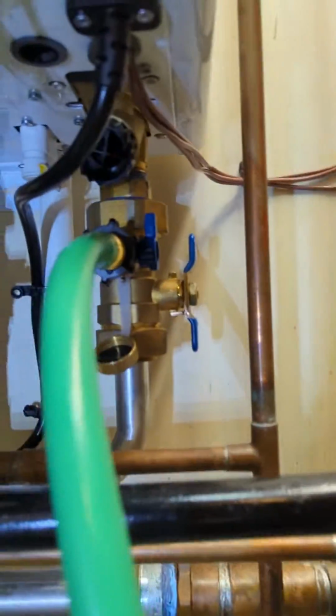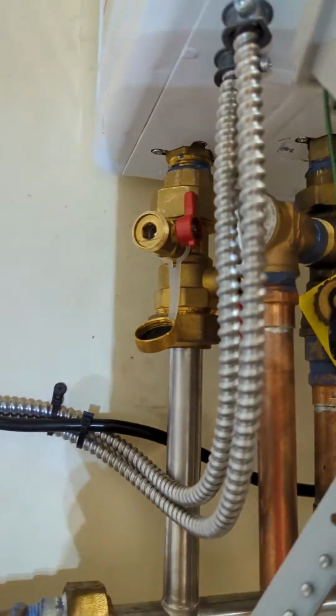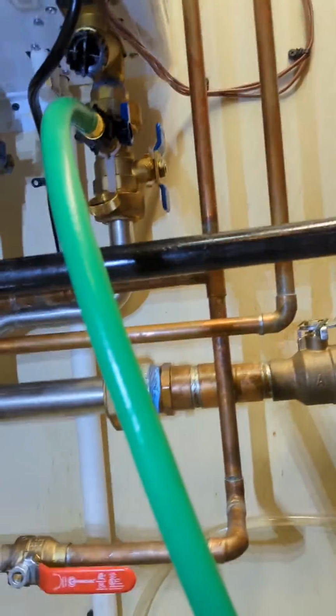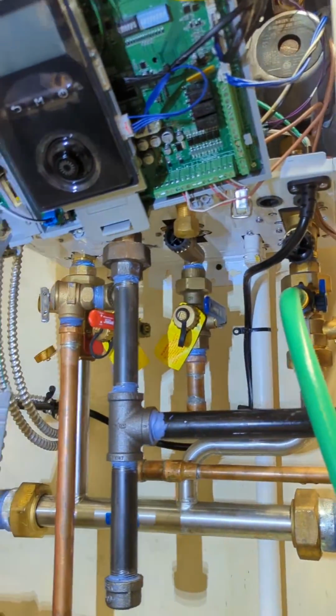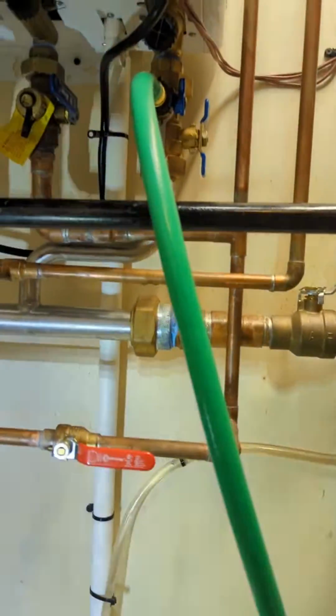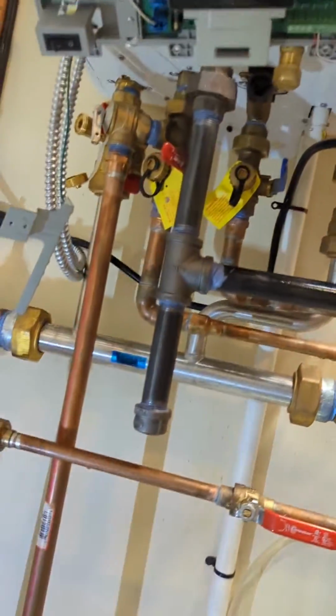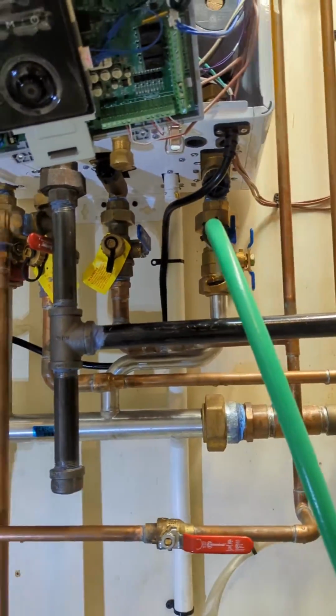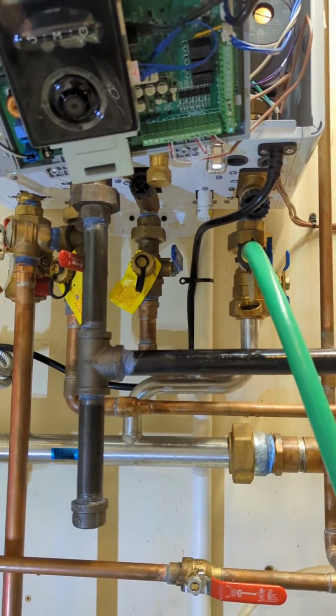If you look at that, that's open and that's open, and then that main feeder is open also, so everything for the pressure side is good. Now we have to bleed the air out. That's very important, you don't want this to run without water in the heat exchanger or it will overheat. So let's do the bleeding side.